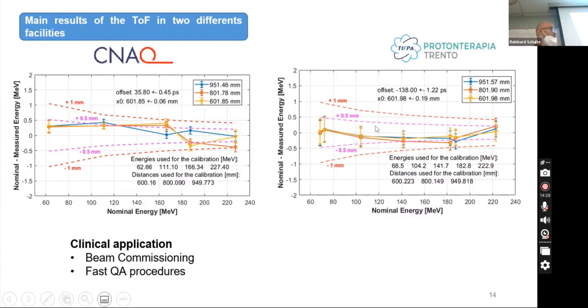We tested at the Trento Proton Therapy Center, and we obtained for all the distances an error of less than 0.5 millimeter of range. I would like to point out that our prototype is almost transparent to the beam, with a perturbation of around 250 micrometers of water range equivalent. Our measurements are very fast. Only a few milliseconds of data were necessary to obtain the accuracy of our prototype, and it was tested in two different facilities, so it is independent of the beam time structure. One of the applications can be beam commissioning and fast QA procedures.